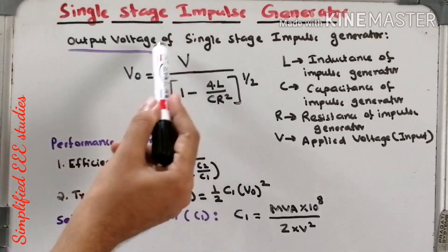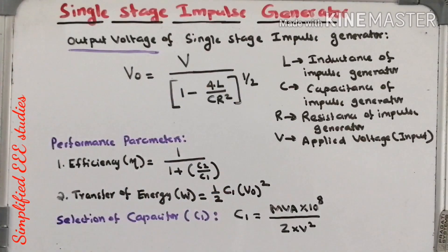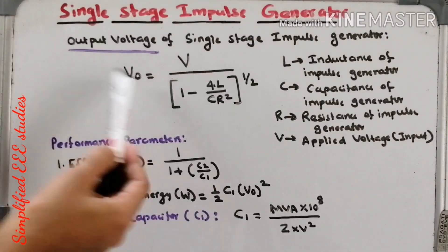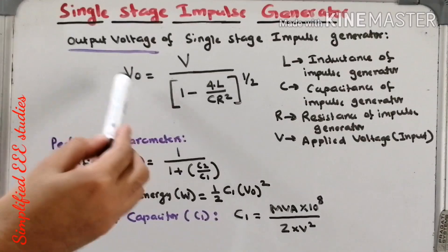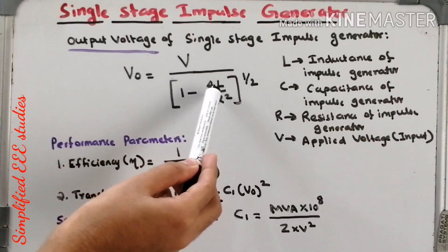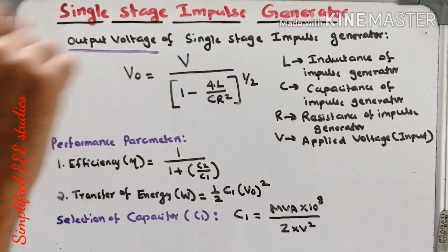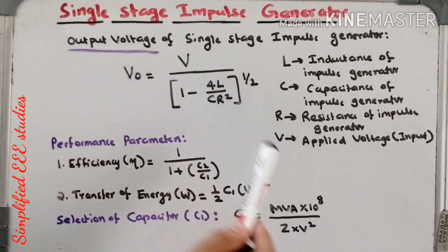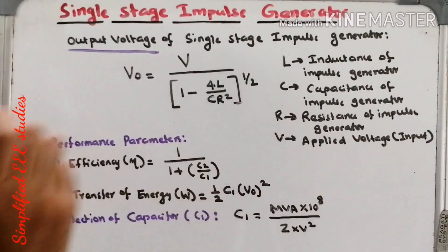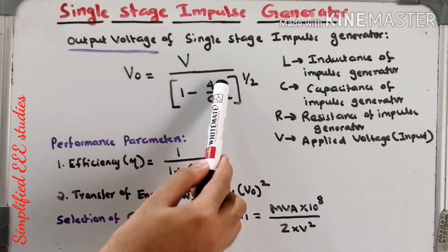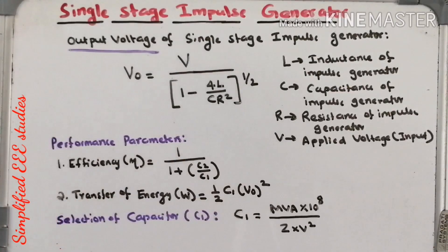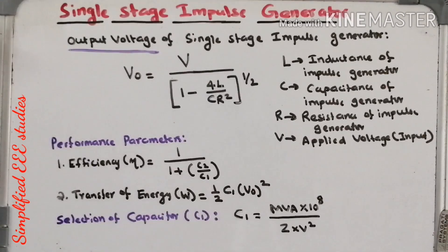We can calculate the output voltage of single stage impulse generator. The formula is: V₀ = V / (1 - 4L / CR²)^(1/2), where V₀ represents output voltage as a function of time, V is the applied DC input voltage, L is the inductance, C is the capacitance, and R is the total equivalent resistance of the given circuit. By using this formula, it is possible to calculate the magnitude of voltage generated from the impulse generator.